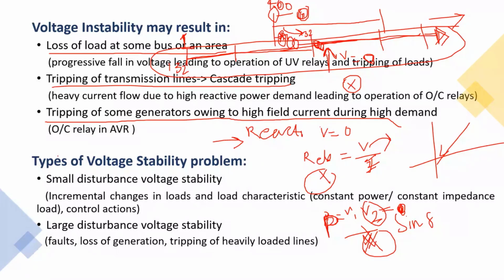So there are two kinds of voltage stability problem that we can face. One is the small disturbance voltage stability problem. Another is large disturbance. For a small disturbance, as I told you, let us start increasing the load one by one. The load keeps increasing and you don't have that much reactive power support in the system. Then this voltage collapse or voltage instability situation will gradually come into the system. So that's small disturbance voltage stability. Large disturbance happens when you have a fault, loss of generation or tripping of a heavily loaded transmission line, those kinds of situations, where it happens suddenly and creates very large voltage changes in the system. In those cases, it is called large disturbance voltage stability.